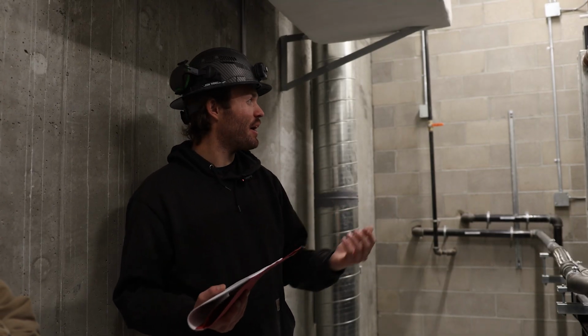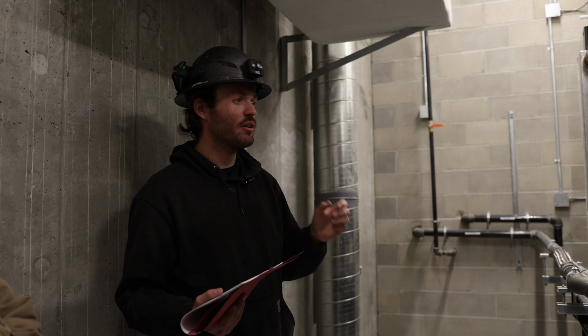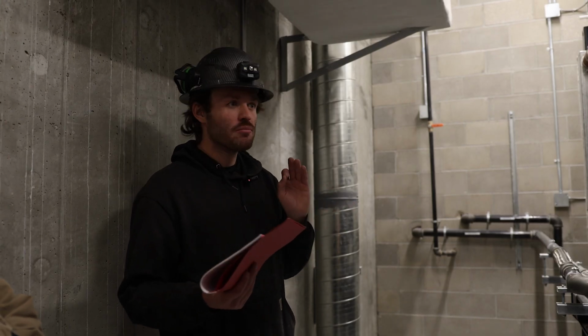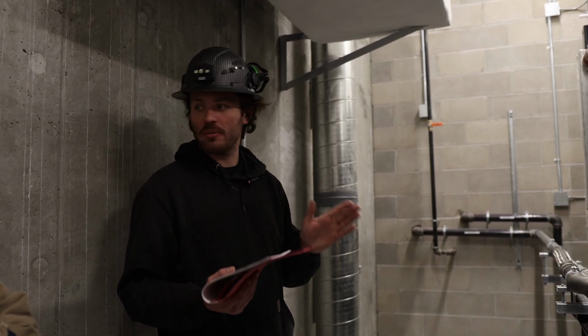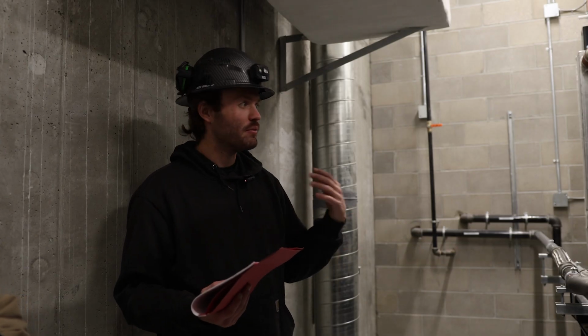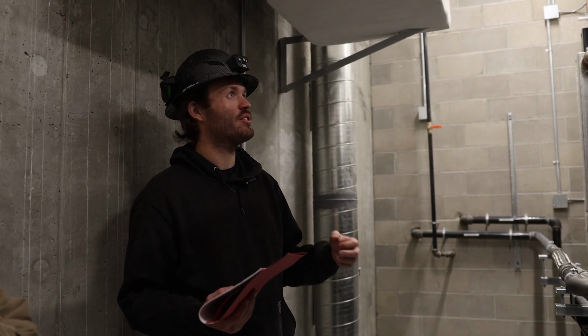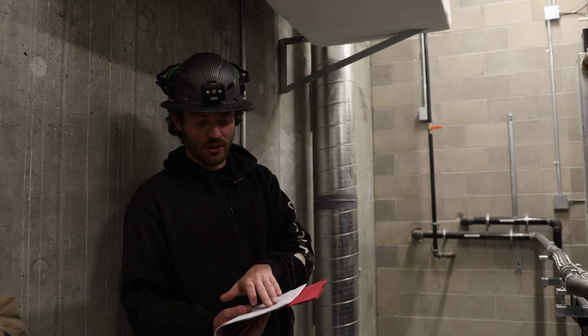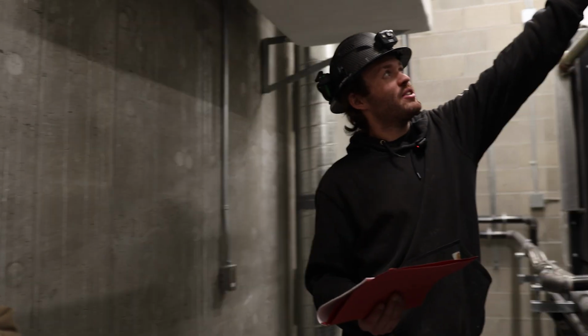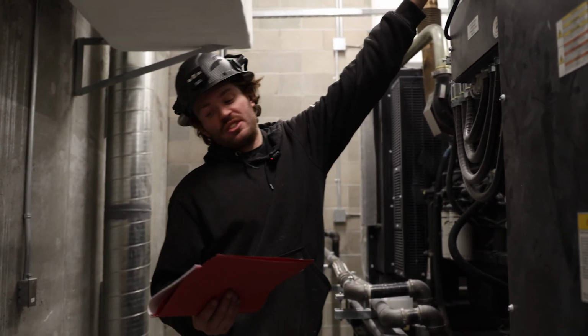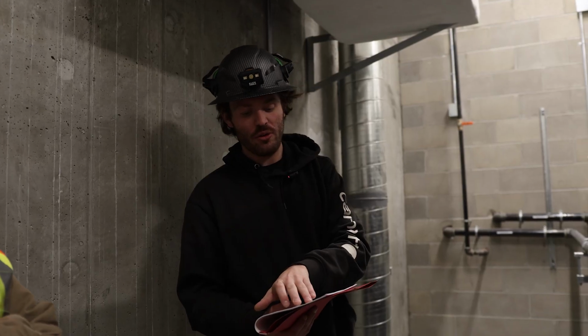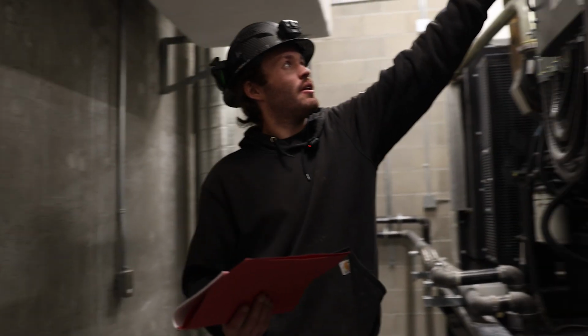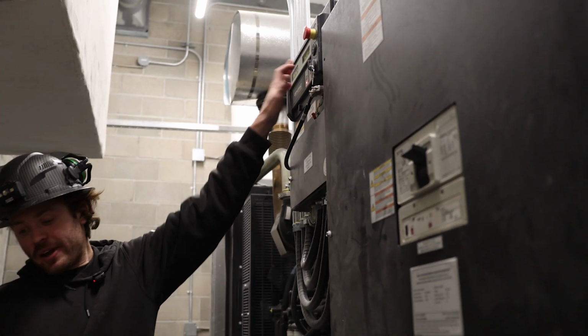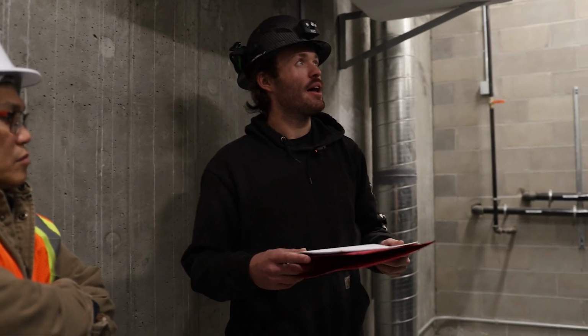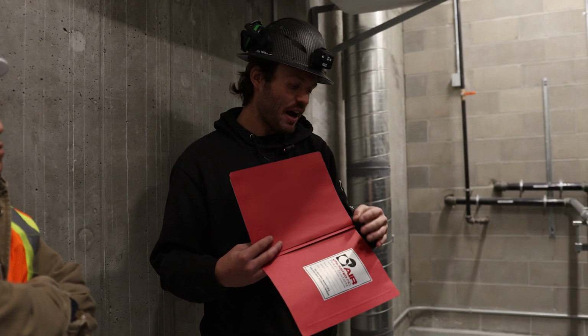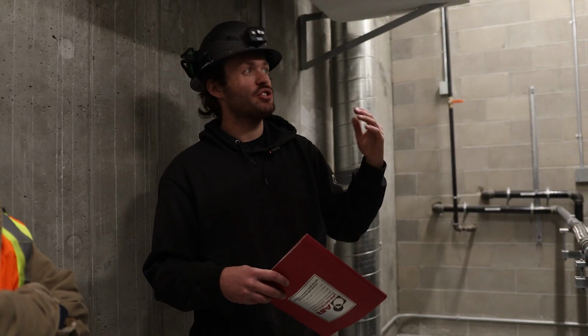When that's happening, come back in the room, inspect once in a while. You don't have to stand here, eyes glued to it for an hour straight, making sure that it's still running, but check it regularly, monitor it, record down your volts, your current, your frequency, everything basically shown in this display. Record down your oil pressure, your coolant temperature, stuff that's all going to be shown in this display.